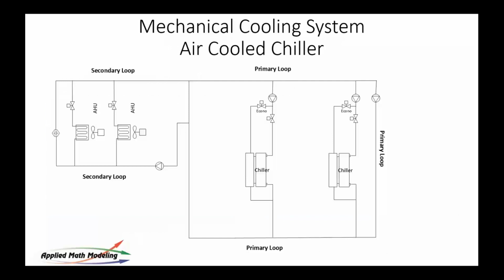This is a diagram of the layout we're going to use. We're going to be using air-cooled chillers on this one. The air-cooled chillers are becoming popular in many places. I see a lot of them in Europe. So this would be like an Airedale chiller. And you see there's an economizer loop here. If the temperature allows, you can bypass the chiller.